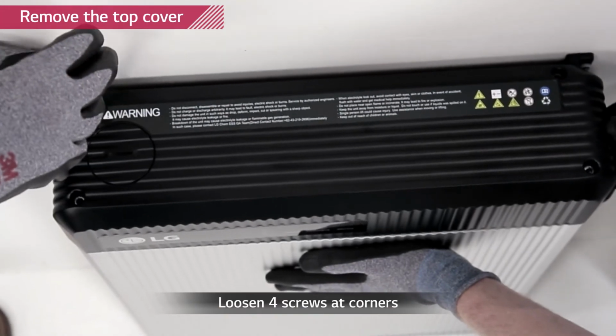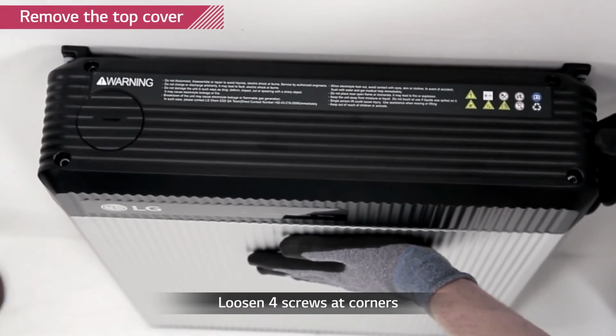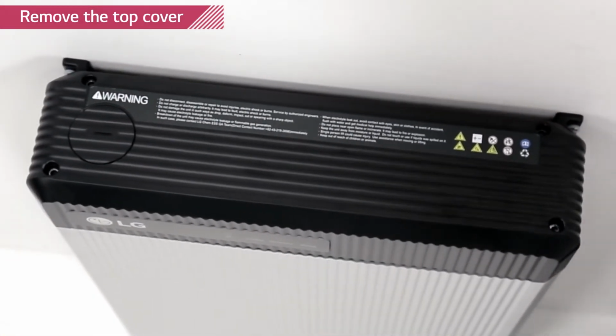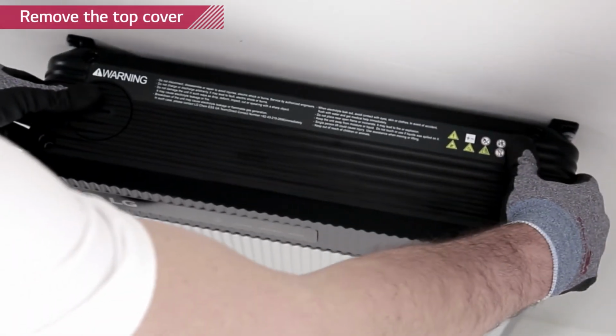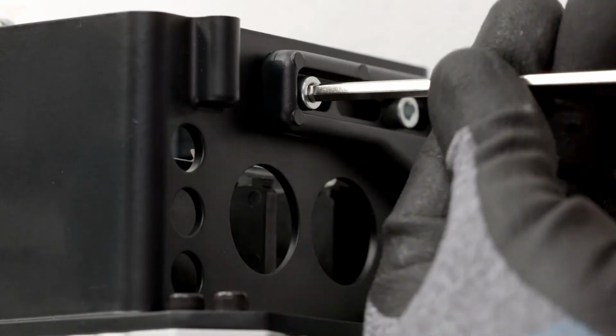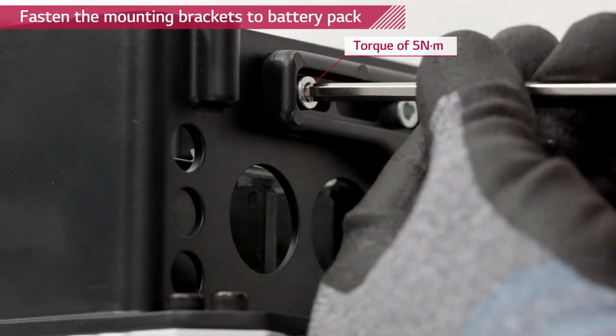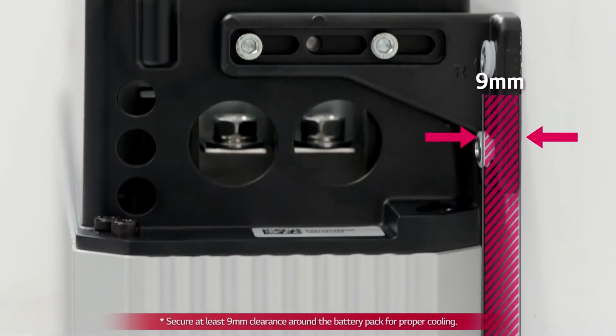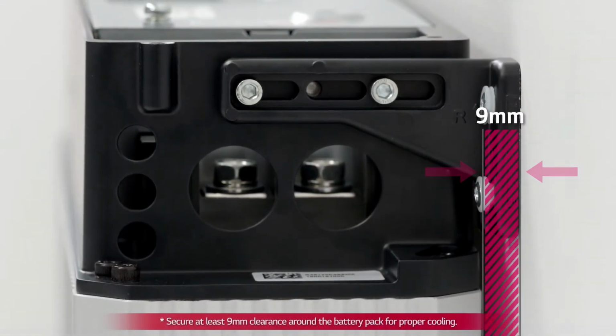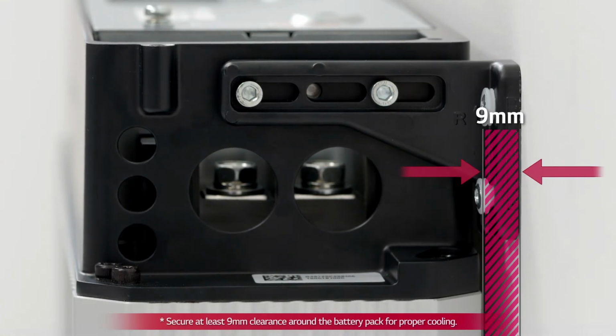Loosen the 4 screws on the top cover and remove it. Fix the RESU battery pack to the mounting brackets using M5 hex socket screws with a torque of 5 Newton meters. Remember that the battery pack needs to have a distance of at least 9 millimeters away from the wall.